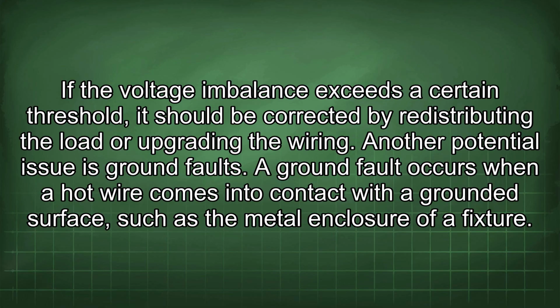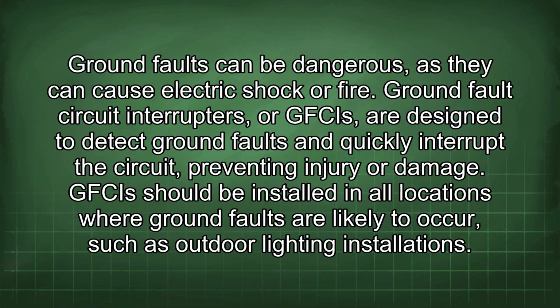Another potential issue is ground faults. A ground fault occurs when a hot wire comes into contact with a grounded surface, such as the metal enclosure of a fixture. Ground faults can be dangerous, as they can cause electric shock or fire. Ground fault circuit interrupters, or GFCIs, are designed to detect ground faults and quickly interrupt the circuit, preventing injury or damage. GFCIs should be installed in all locations where ground faults are likely to occur, such as outdoor lighting installations.